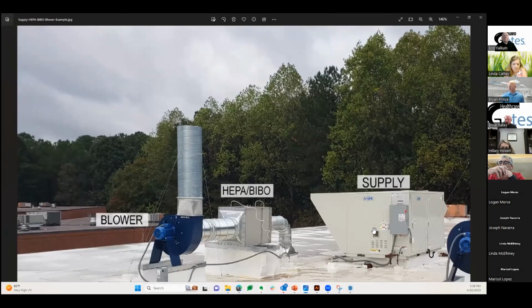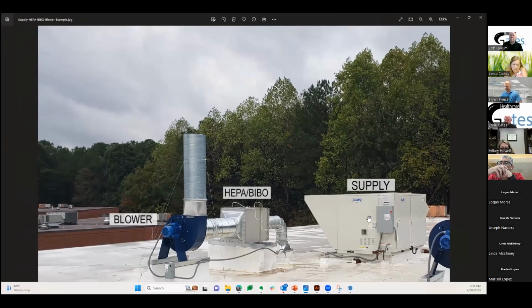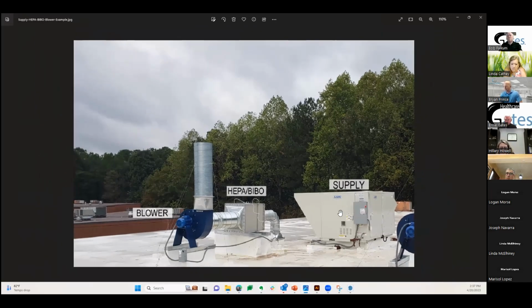These air handling units typically come with pre-filters and primary filters, but they're all MERV rated. The pre-filters are MERV 8s, and the primary filters are MERV 13s. Keep in mind, a MERV is not a true HEPA, and they're also not gasketed. During heavy pollen season, like we're having right now in the South, those pre-filters need to be changed at least monthly because they become impacted, or if you're near an industrial site catching heavy particulate. So it's one thing to manage here, but also good to manage at the ceiling level.